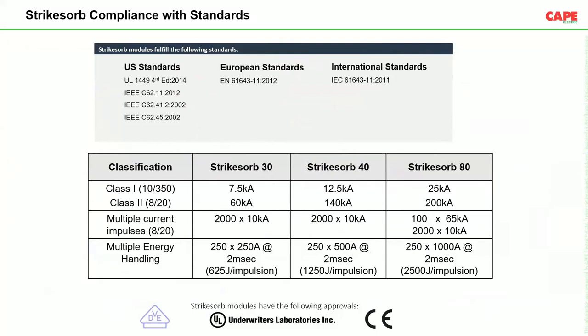Please note that in the table, classification, class 1 is 10/350, class 2 is 8/20, multiple current impulse is 8/20. So your question is about this multiple current impulse. Strikesorb 30. This model is 2000 into 10 kiloampere. So 10 kiloampere strike, 2000 numbers. Probably once there is a discharge, the capacitor has to be charged again to make the next stroke, so after each discharge it needs some time. If someone is working an 8 hour shift, per day he may be able to make maybe 50 strikes. So into the number of days you can calculate. These are made in this fashion.